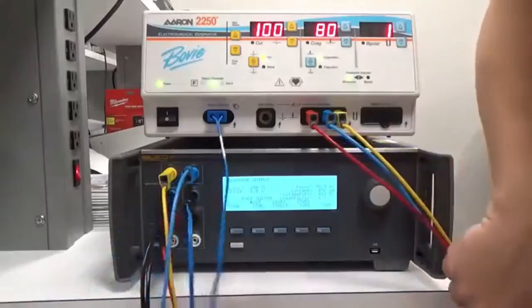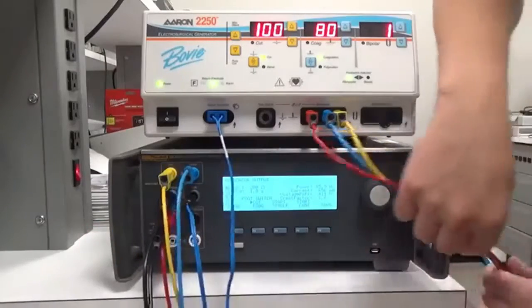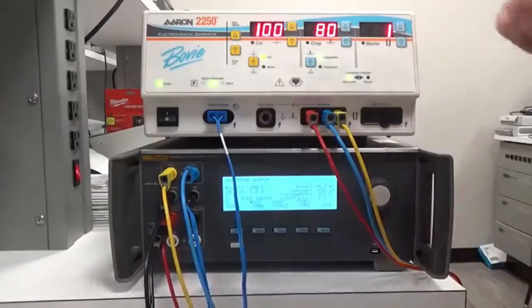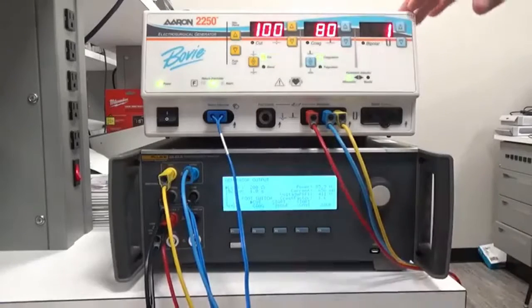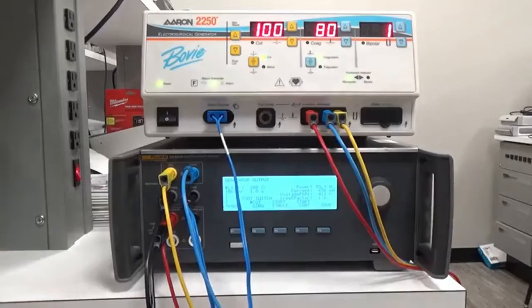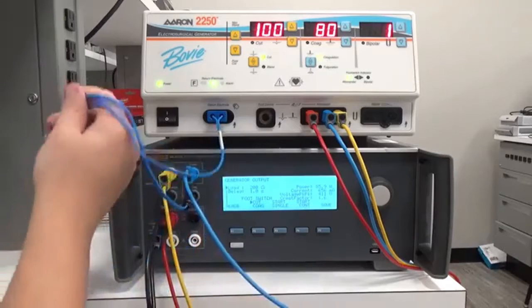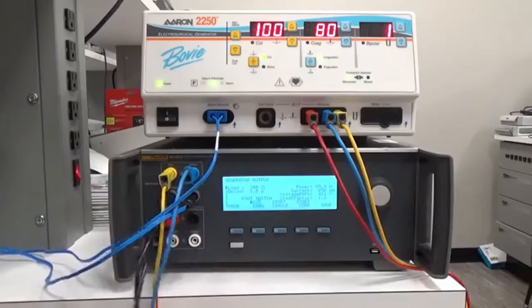So I have all my connections made. The only connection you don't see, on the back of my ESU, I have a foot switch that's connected. Now this foot switch, I'm not actually going to be pressing the pedals when I do the testing. The foot switch automatically engages the ESU when I go and start the test.